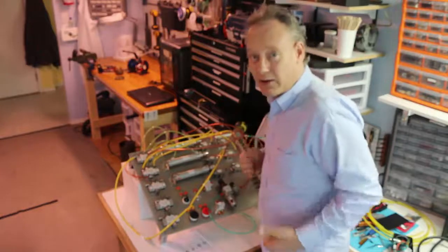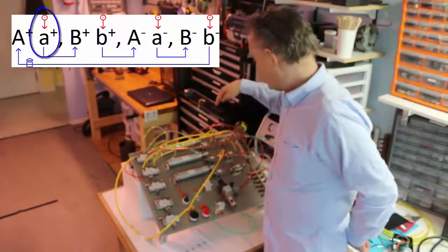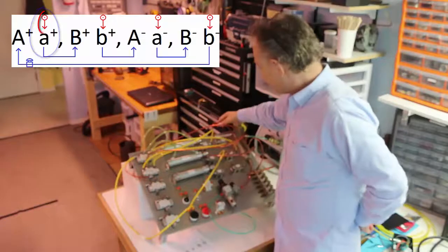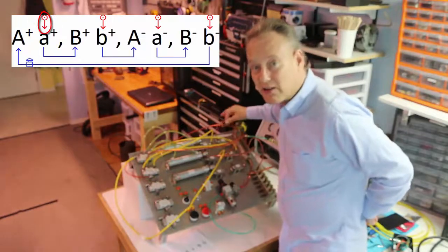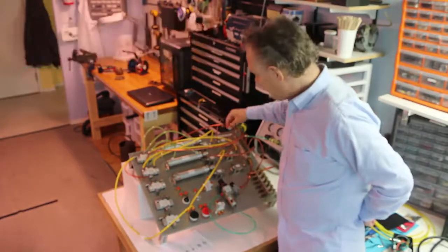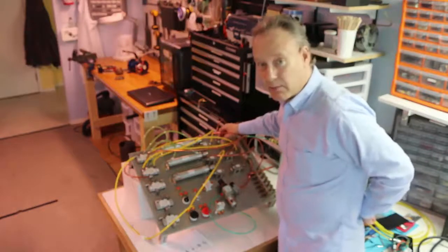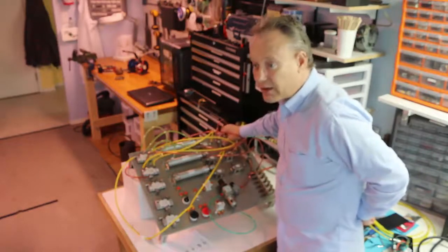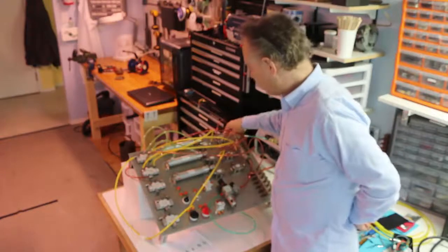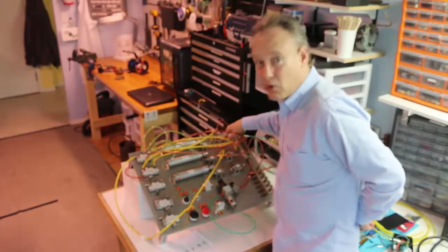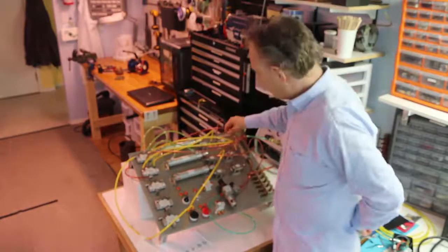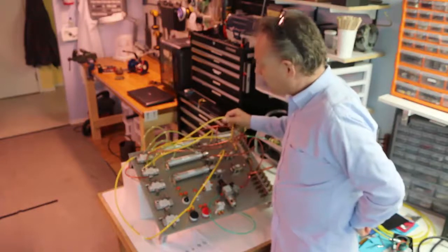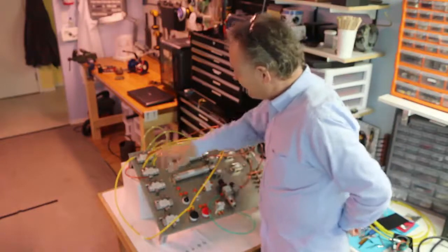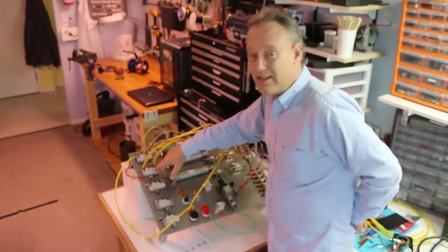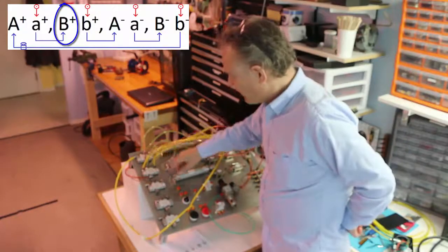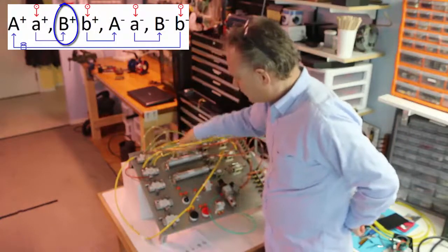When it goes out, this limit valve, which has air in it already, it has air supplied to it, it is not passing. But if I close it, it becomes passing. So right now, that is a closed valve. It's actually a normal closed valve. And when I activate it, it becomes open. Oh look, when it comes open, it then tells the spool in this DCV to move, and now air comes out here and it goes out there.